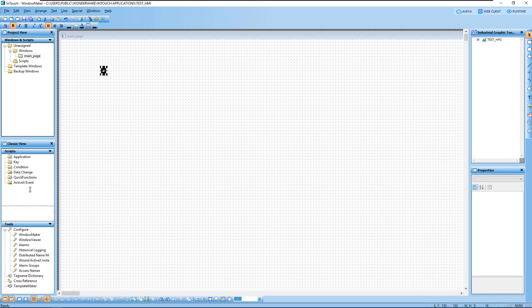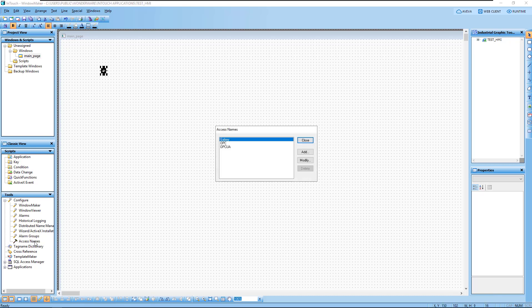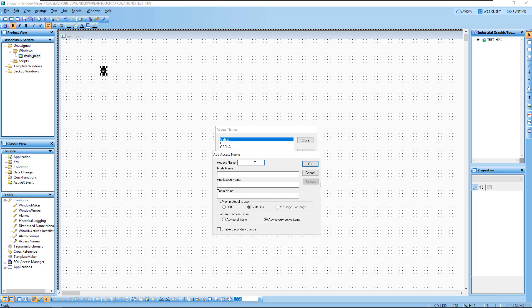First we need to add the access name in the application. Double-click on Access Name and click Add. I'll name the access name 'modbus'. The node name is 'localhost', so I can leave it as is. The application name is the driver name itself — 'MBTCP' — and the topic name is 'Topic0'.